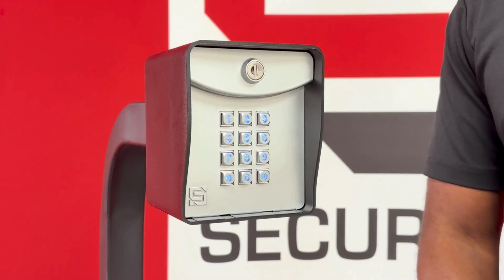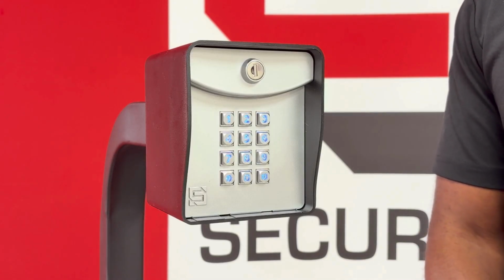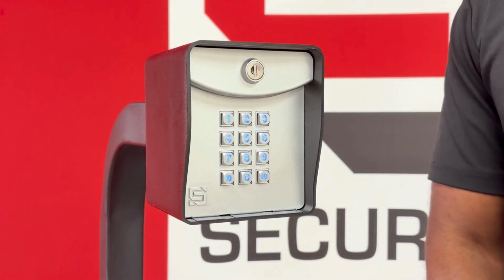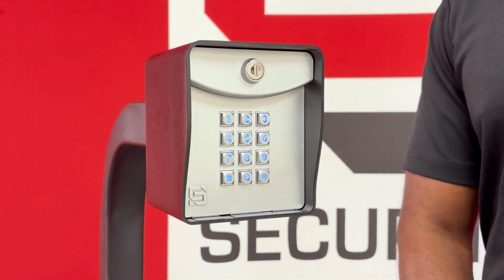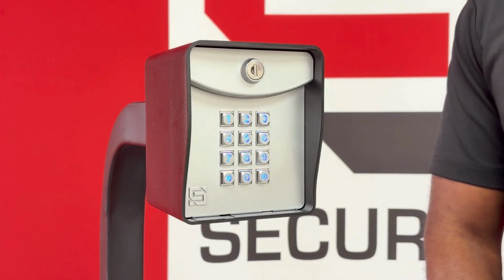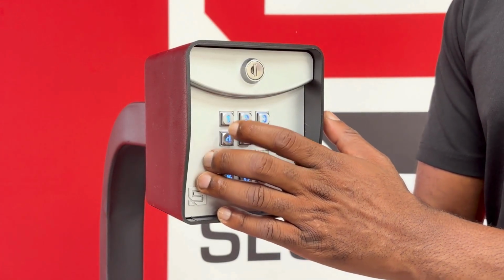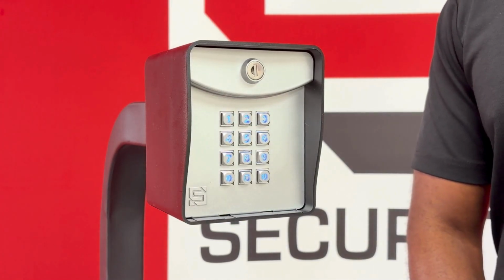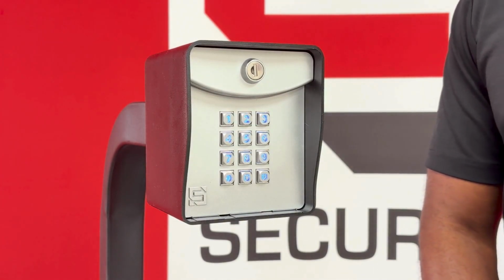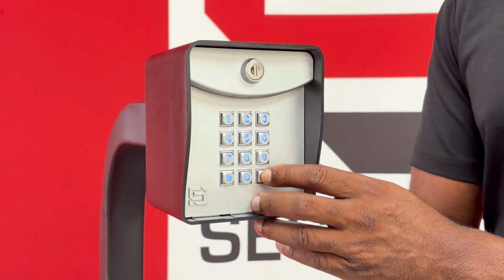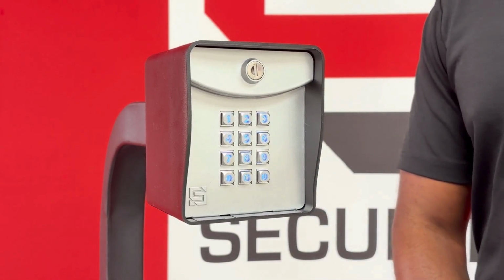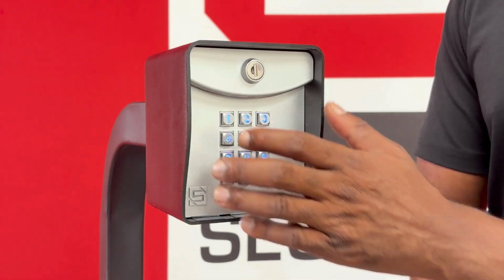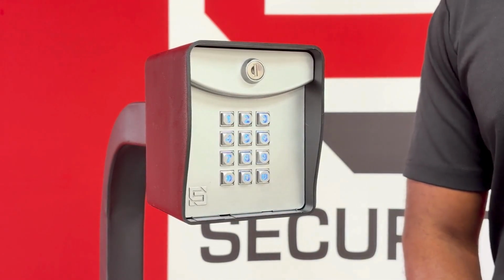We're going to enter the submode for adding a code, which is submode 1. And then we're going to add the code that we want to use. For this example, we'll be using 1414. I've got positive confirmation on all my entries, so I'm going to go ahead and hit pound to exit out of programming mode, and then we'll test that code out. All set.